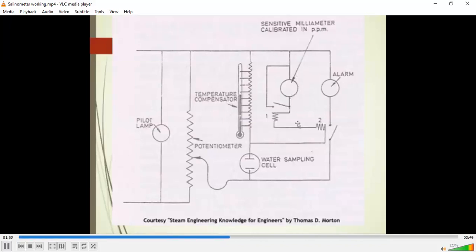Basically, it measures the current, and more current means more impurities. This measures the impurities of the water sample. When the impurity content in the water sampling cell exceeds a fixed value, the current is sufficient to operate relay number 2, closing the switch and giving out an alarm. The current will also pass through into the milliammeter and show the reading.